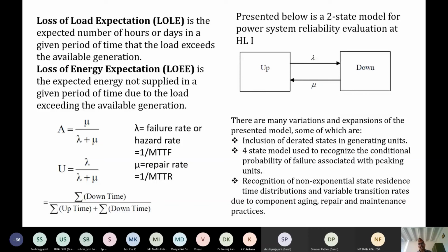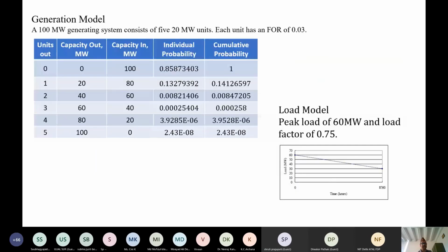We have to adopt different models. Means we have a 2-state model here, there might be a 3-state model, 4-state model, and theoretically n-state models. So generation model means models associated with the generating unit. You can see a force outage rate of 0.03, 5 units of 20 megawatt, means a 100 megawatt generating station or generating system.